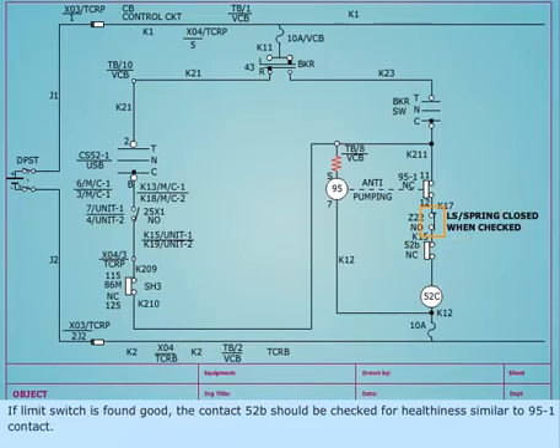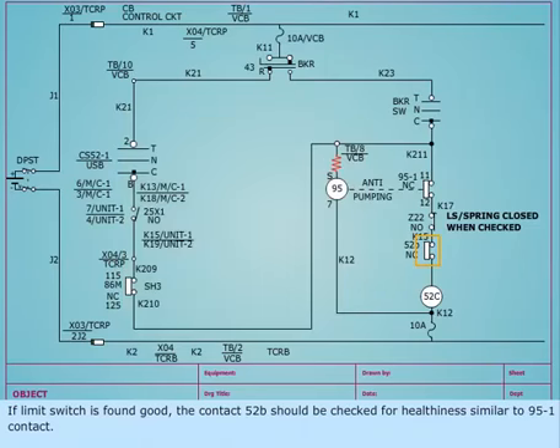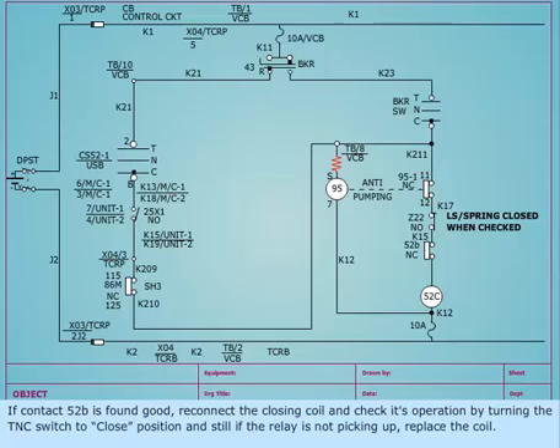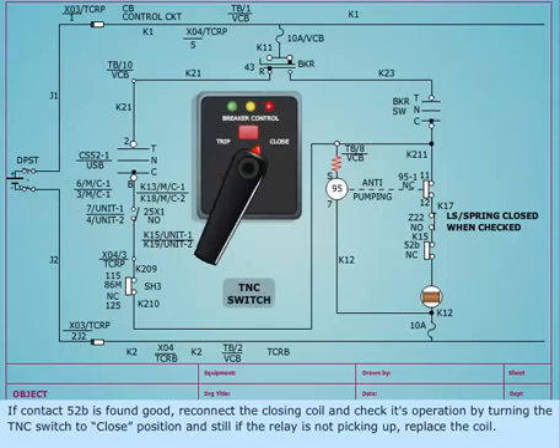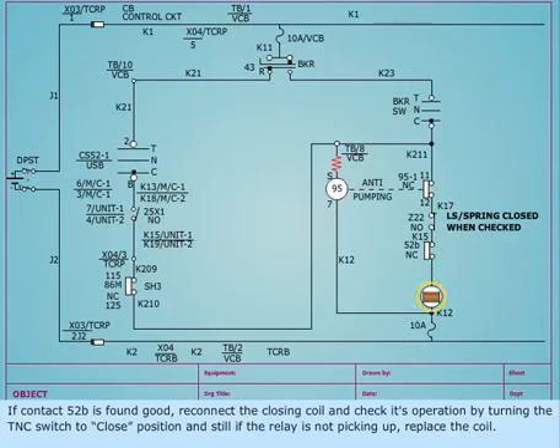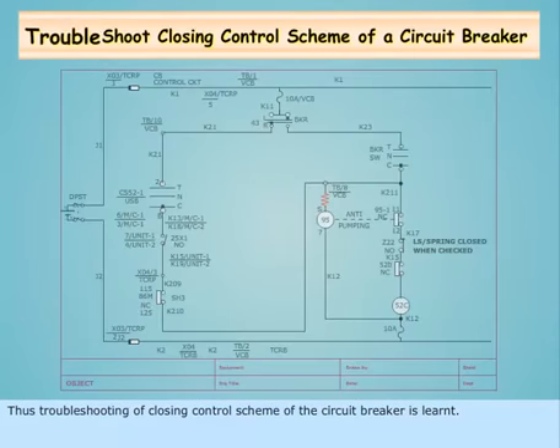If the limit switch is found good, the contact 52B should be checked for healthiness similar to 95-1 contact. If the contact 52B is found good, reconnect the closing coil and check its operation by turning the TNC switch to close position, and still if the relay is not picking up, replace the coil. Thus, troubleshooting of closing control scheme of the circuit breaker is learnt.